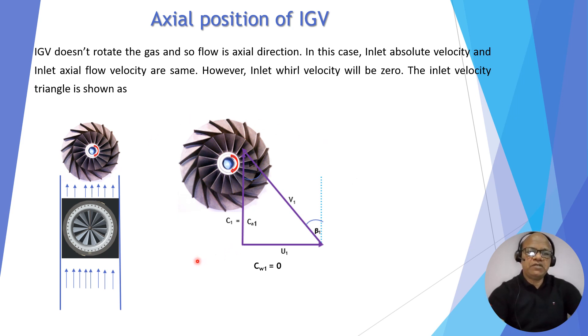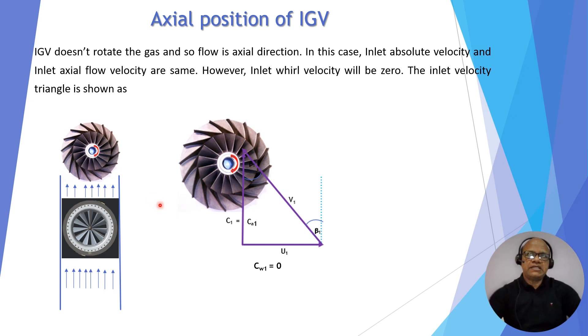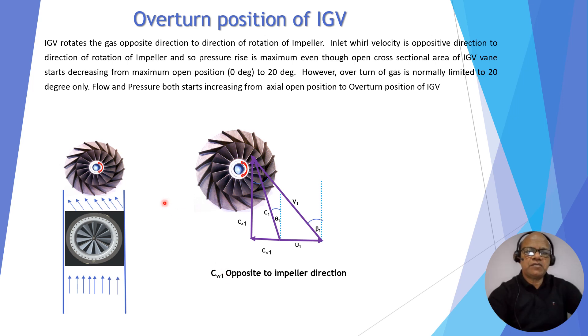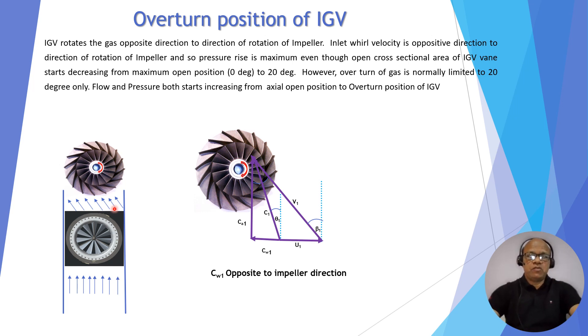For the axial position of IGV, the gas comes in axially and also comes out axially. The gas reaches the impeller inlet in the axial direction. In the velocity triangle, C1 equals CA1, with V1, U1, and CW1 equals 0 because it is axial. For the overturned position, the direction has changed to counter-clockwise relative to the impeller — that is, opposite to the direction of rotation — and this is limited to 0 to 20 degrees only.